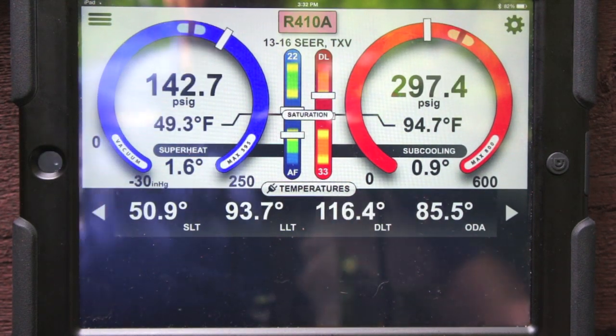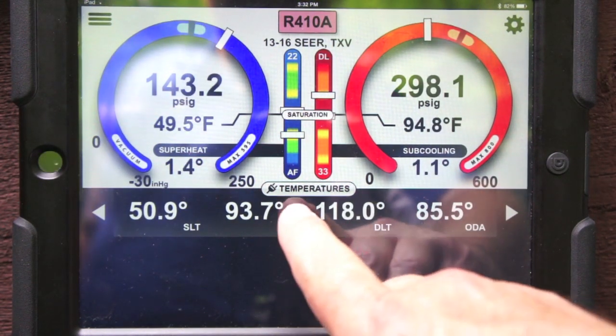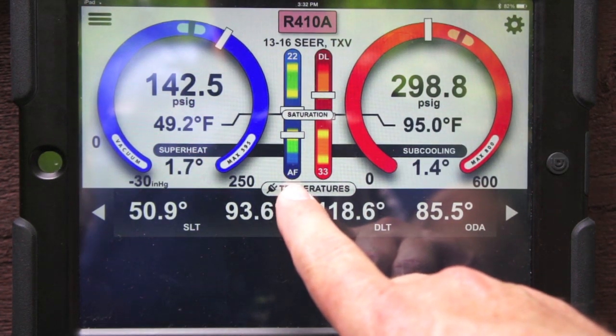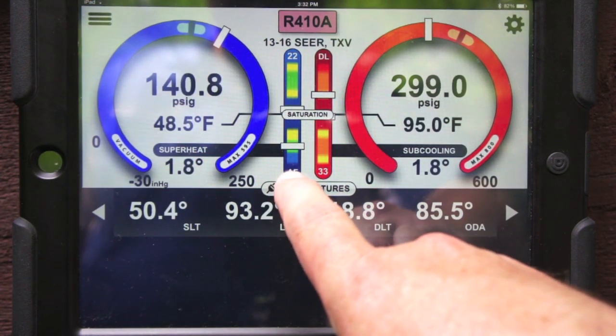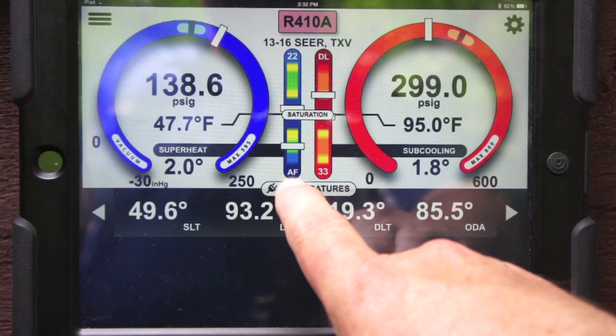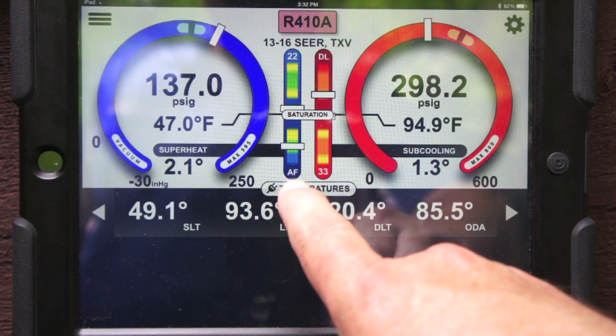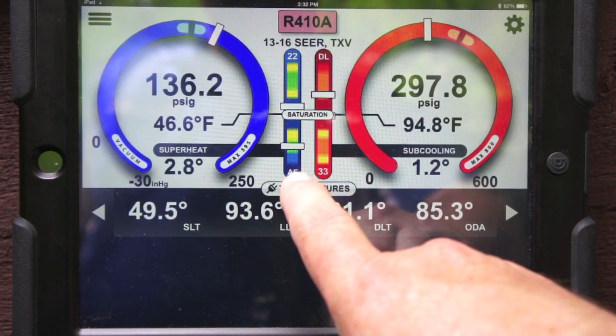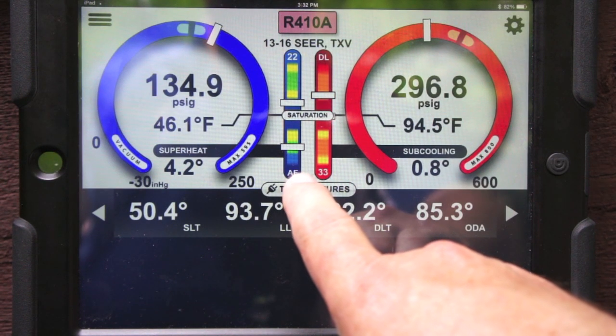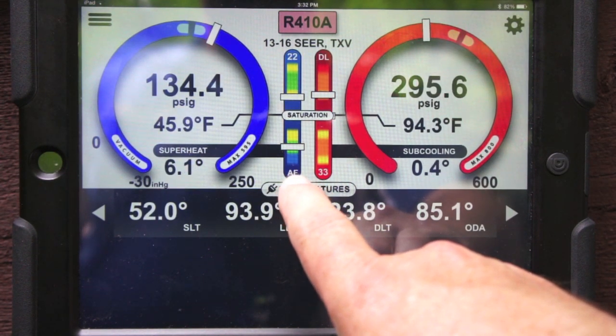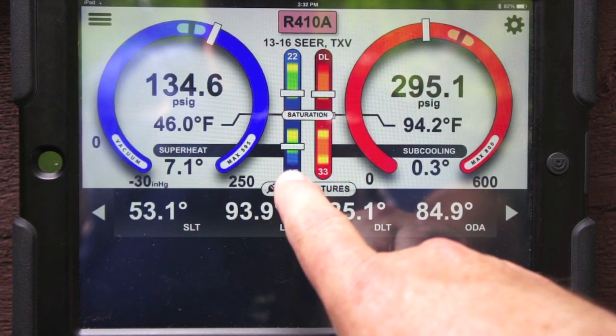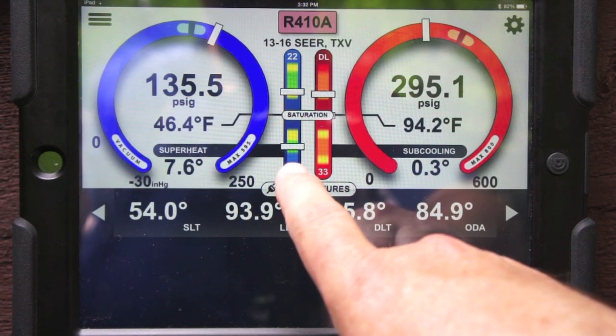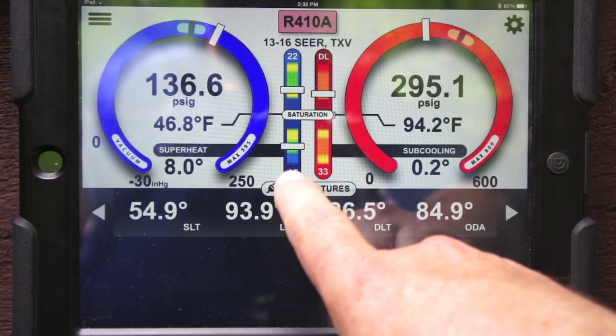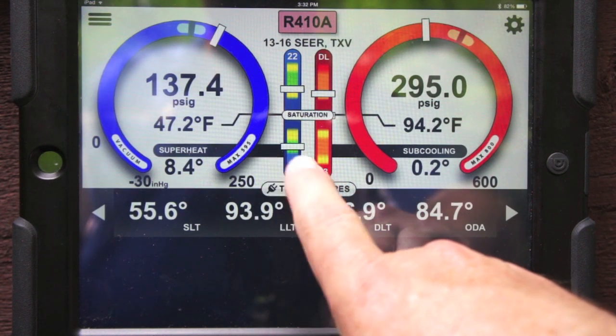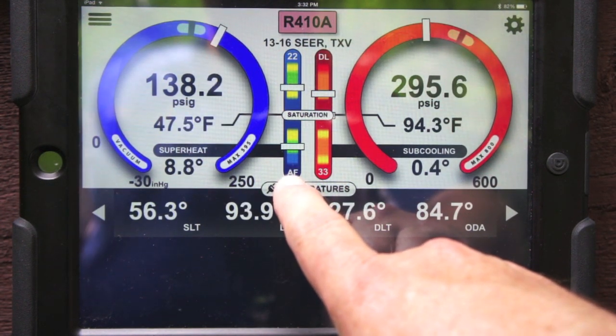And now that we're started here, I want you to notice a couple things here. We've added some really cool features in that'll really help you diagnose some problems here. The airflow indicator, AF, that I'm looking at right here, shows you if you have enough airflow to properly charge the system. This is working off of our temperature split. So it's looking at temperature split of the system, and if it's in the blue, that means the airflow is too low and that we need to adjust the airflow before we continue to charge.